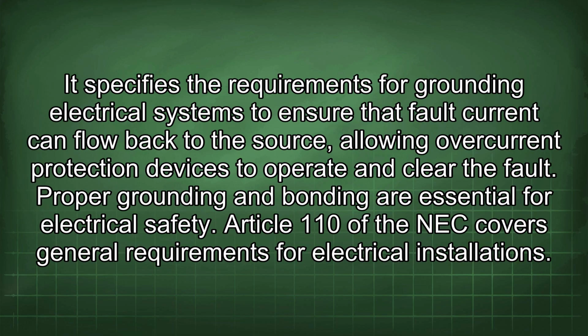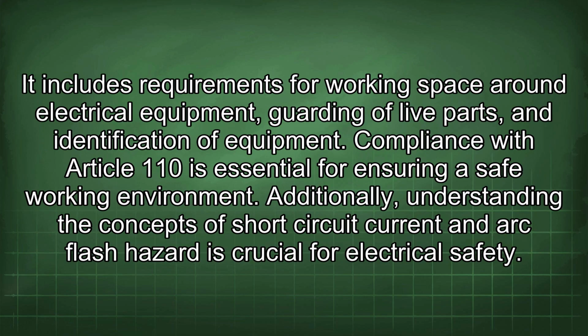It specifies the requirements for grounding electrical systems to ensure that fault current can flow back to the source, allowing overcurrent protection devices to operate and clear the fault. Proper grounding and bonding are essential for electrical safety. Article 110 of the NEC covers general requirements for electrical installations. It includes requirements for working space around electrical equipment, guarding of live parts, and identification of equipment. Compliance with Article 110 is essential for ensuring a safe working environment.